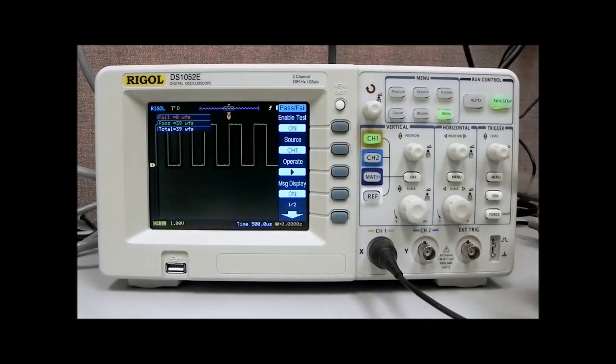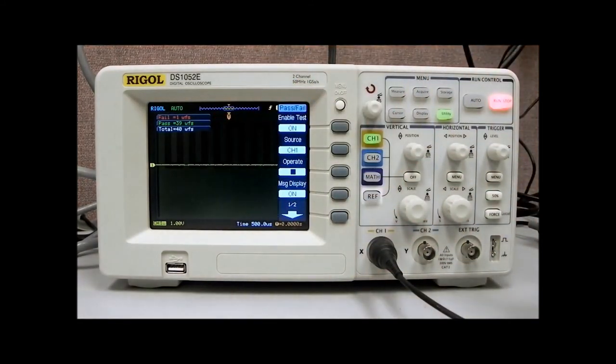And you'll see it will quit taking waveforms. So we've gone into stop mode, and now we've only had one fail, but that fail has stopped the instrument from taking any more data.